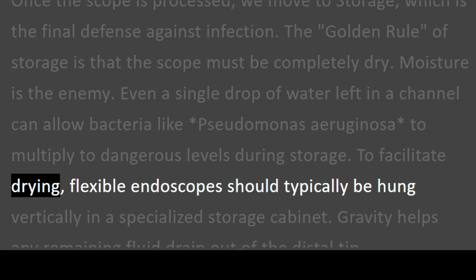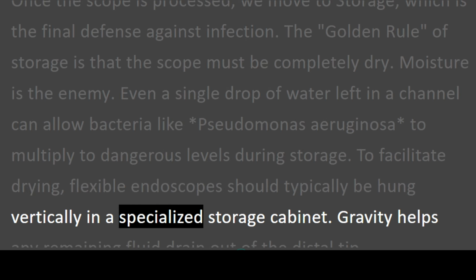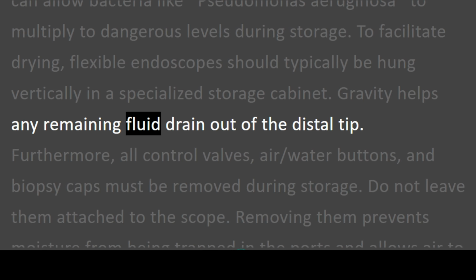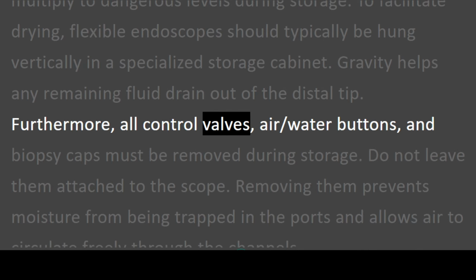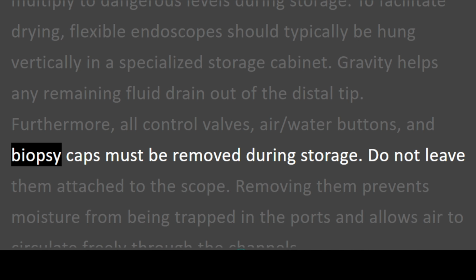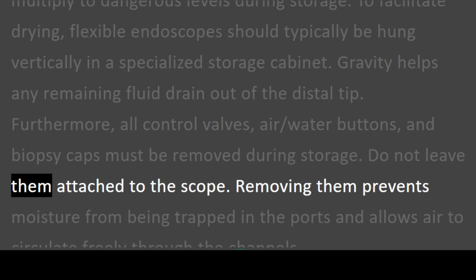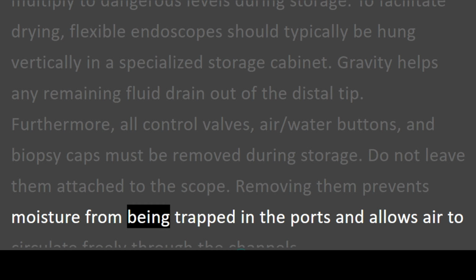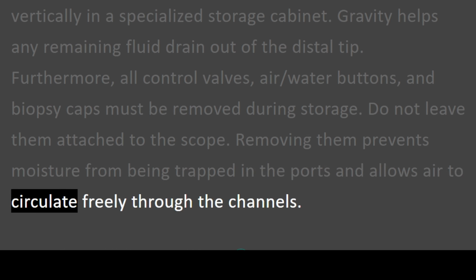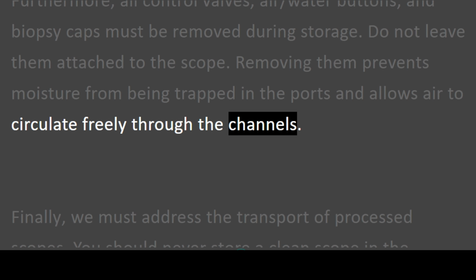To facilitate drying, flexible endoscopes should typically be hung vertically in a specialized storage cabinet. Gravity helps any remaining fluid drain out of the distal tip. Furthermore, all control valves, air/water buttons, and biopsy caps must be removed during storage. Do not leave them attached to the scope. Removing them prevents moisture from being trapped in the ports and allows air to circulate freely through the channels.